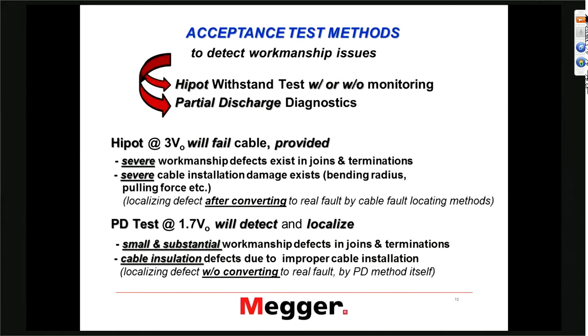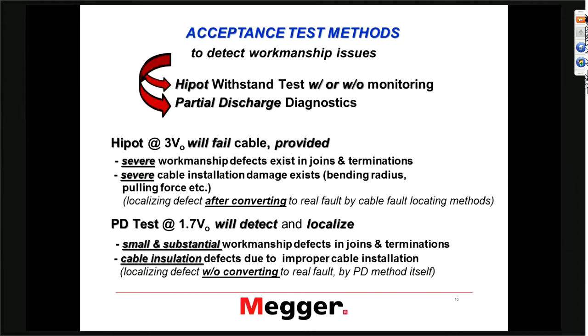Today, for the most part, the DC hypot test is superseded by the VLF type AC hypot test. That had to do with the fact that we are dealing with solid dielectric cables, which don't take very well to DC hypotesting. If we do a regular hypot test according to IEEE 400.2, the voltage specified is 3 per unit, where V0 is the phase voltage to ground. That is typically the voltage specified for a 0.1 Hz VLF test set.